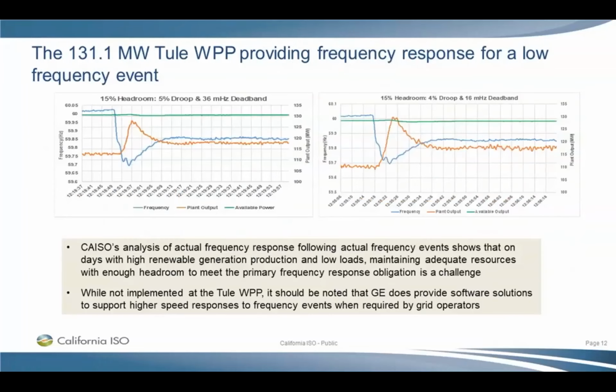What's really important on this plot is that it shows frequency response, frequency control. Again, these are actual events that we had in the Western Interconnection. The blue is an actual frequency drop that we fed into the plant controller. And you can see how well this wind plant was able to increase megawatt output. Again, you need to have a certain amount of headroom available. So this plant was able to respond to that low frequency event very well.